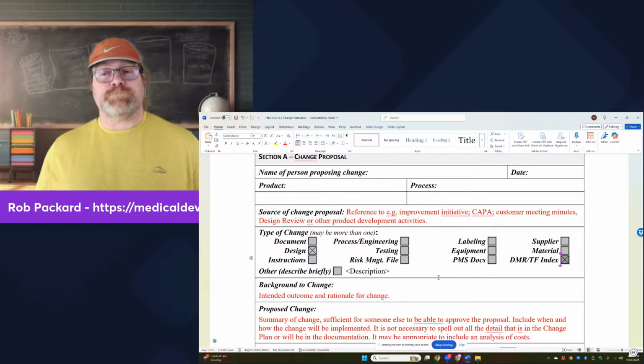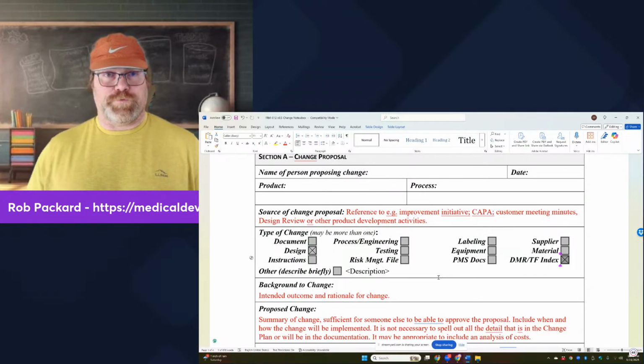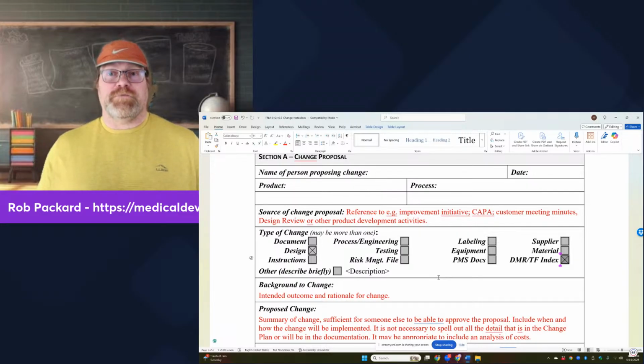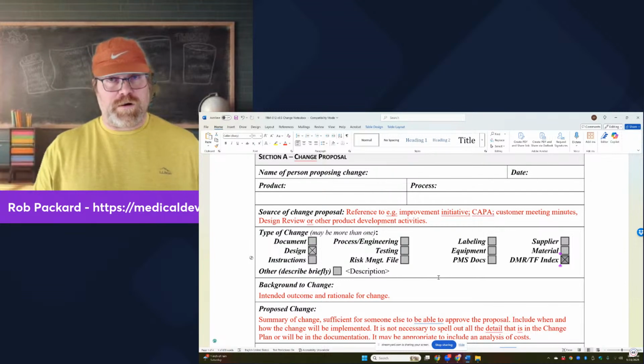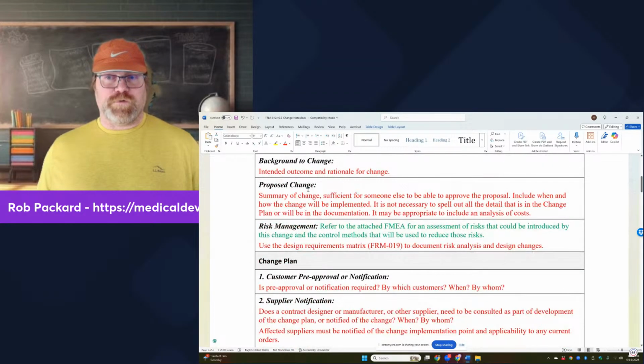approval. Sometimes they don't, and you can make a justification for why you don't need regulatory approval, because it falls within the FDA guidelines of this is something that's documentation only. And the documentation would be this form plus the letter to file form justifying why a new submission is not required. And this is not a one-page form, it's a 4-page form.